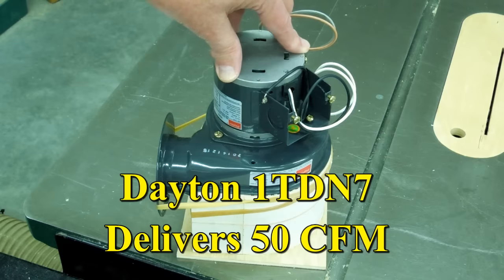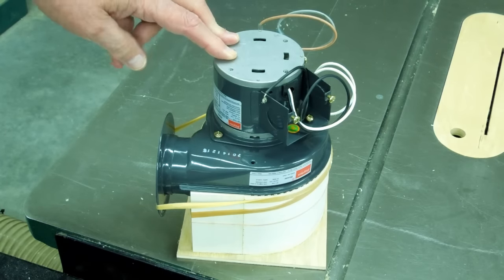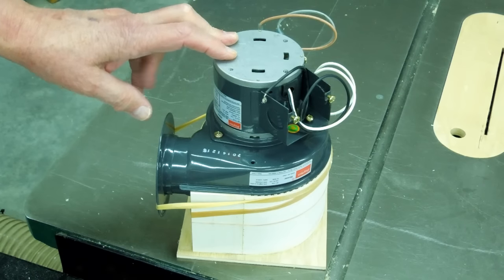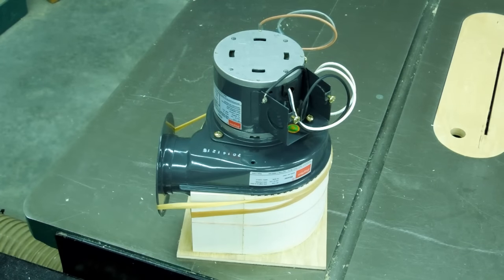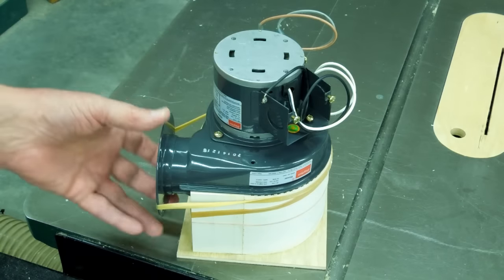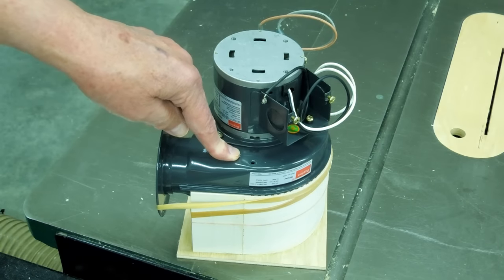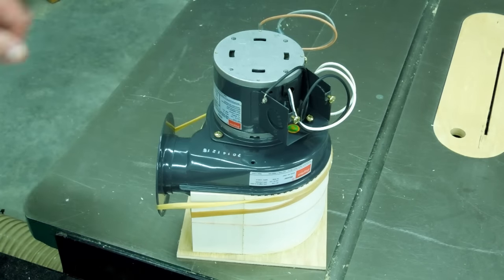This is a small 110 volt Dayton squirrel cage blower. This will deliver 50 cubic feet a minute with no resistance, that means no back pressure and no resistance on the suction side. These do not have a flange on the suction side, they're generally expected to be drawing free air.